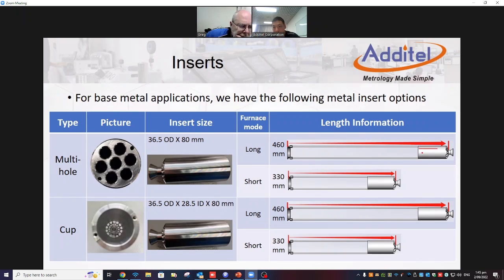So the hole is right here, and the entire length of this part is not that big. So maybe when we do the testing, the end side of the furnace is right here. The tip right here to the open side of the furnace is maybe over 200 millimeter. So the gap between the hole and the probe is definitely no problem at all, because the gap will be filled by the hot air, and the hot air is pretty far away from the heat leaking point, so we don't need to worry.